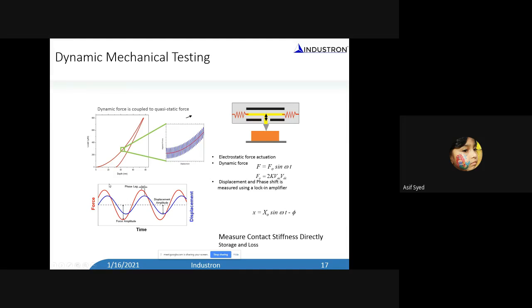The force and the displacement will totally overlap with each other. There won't be any phase shift. But if you do it on a viscoelastic material like polymers, you will see this phase shift. The displacement will lag behind the force. When you apply a force, it takes a little bit of time for the material to respond. So the displacement will lag behind the force. And if you measure this phase lag, you can calculate the loss component of this viscoelastic material.